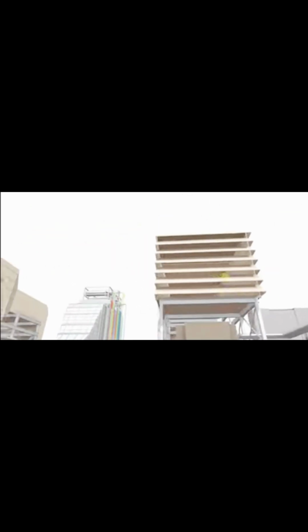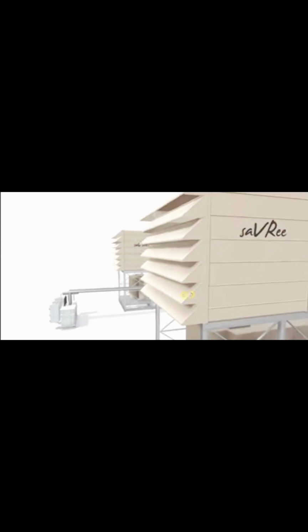We draw air in through these louvres here, and the air will pass through a series of filters before it gets to our gas turbine. We filter the air because we don't want any foreign particles being sucked into the turbine, because that might damage our compressor blades or our turbine blades. So it's important to filter the air. It's also important to de-ice the air to make sure no water or moisture is sucked into the turbine.